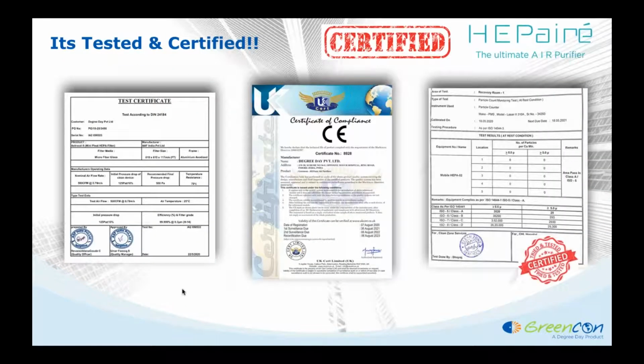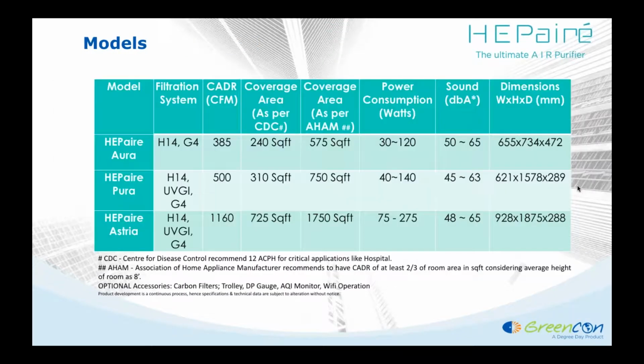Every unit would come with a test certificate of the filter which is being used, which specifies the class and the result, certified. And on the right hand side, this was a case where a doctor has actually utilized it for an operation theater, and you can see that the results were absolute zero of any kind of particles, and it was classified under ISO 5.